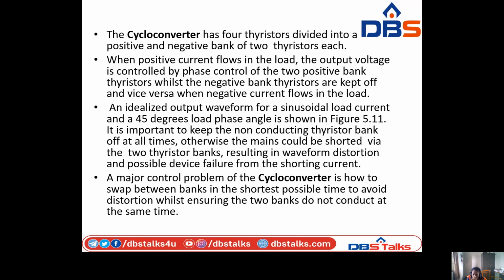So the major control problem of the cycloconverter is how to swap between the banks in the shortest possible time to avoid distortion, while ensuring the two banks do not conduct at the same time.